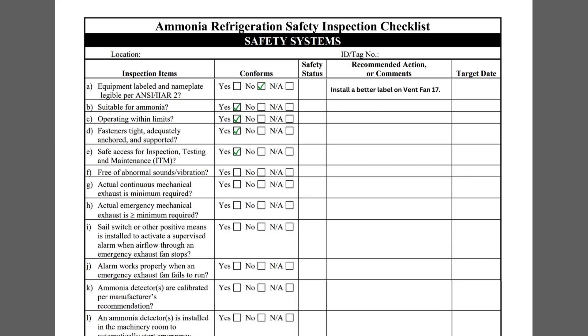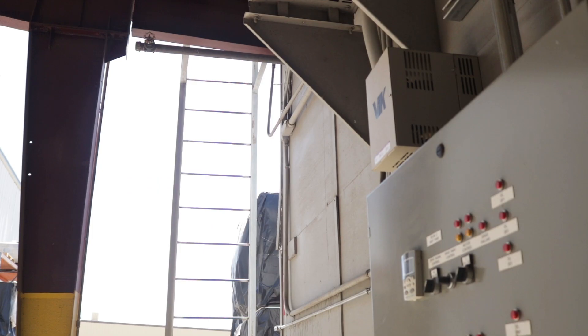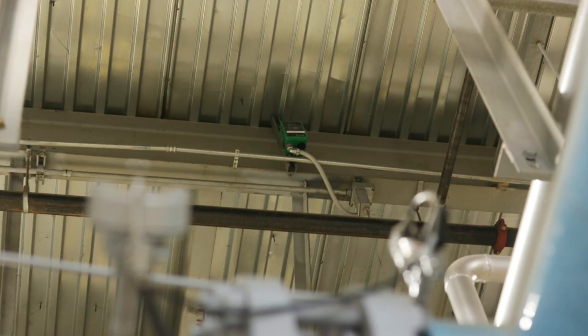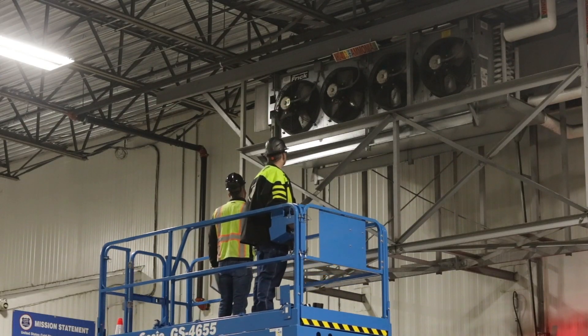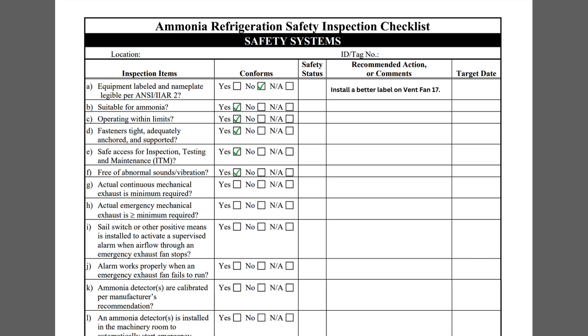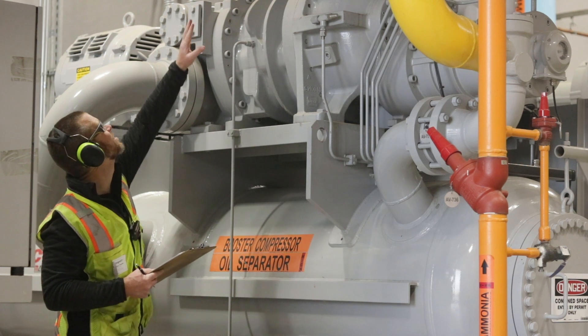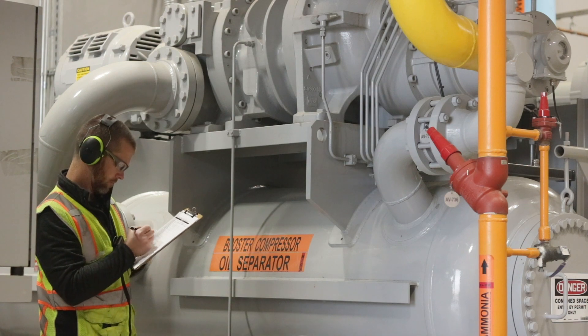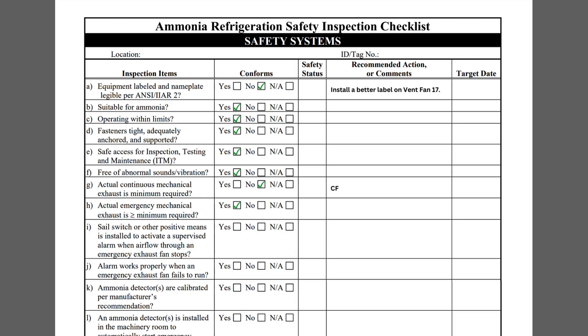The safety system should have safe access for normal service and maintenance. Ideally, permanent ladders, catwalks, or other means of access to the equipment will be available. Some detectors are located at the ceiling and may require an extension ladder or aerial lift to access. Checklist Item F is specific to leaks and other equipment deficiencies. The inspector must do a visual inspection of the system to verify the equipment is free from any abnormal vibration, sounds, or leaks.